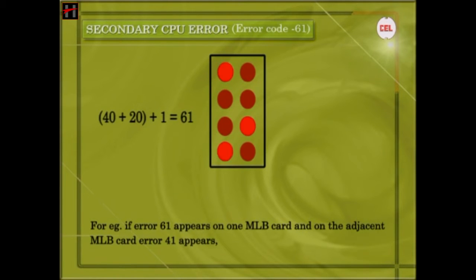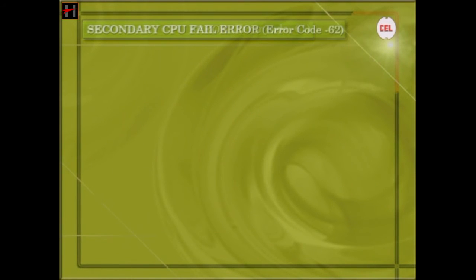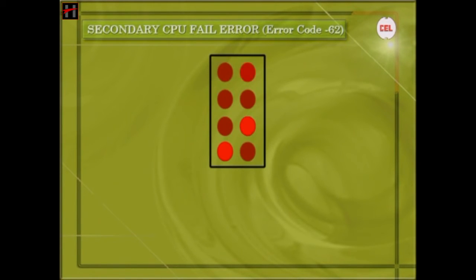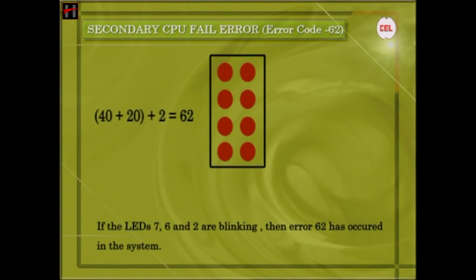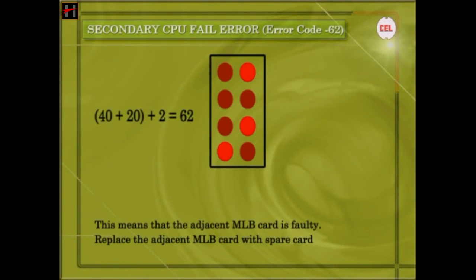For example, if Error 61 appears on one MLB card and on the adjacent MLB card Error 41 appears, then carry out the checks for Error 41. Secondary CPU Fail Error: If LEDs 7, 6, and 2 are blinking, then Error 62 has occurred. This error is generated if any of the CPUs fails to respond with its adjacent CPU due to failure of any components. This means that the adjacent MLB card is faulty — replace the adjacent MLB card with a spare card.